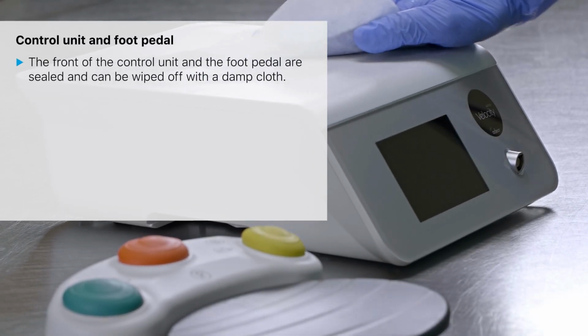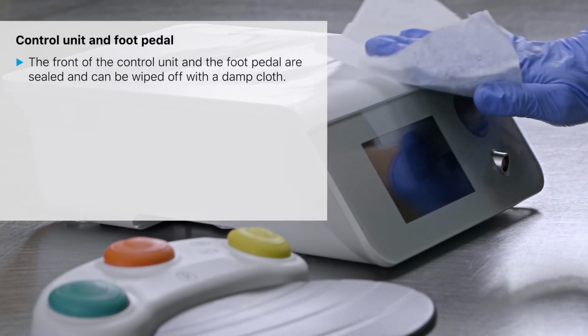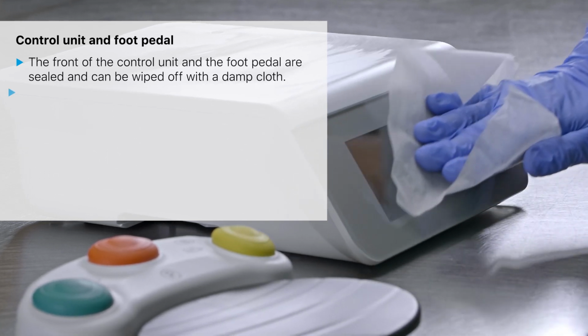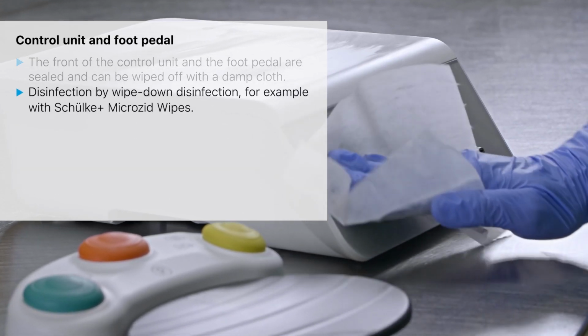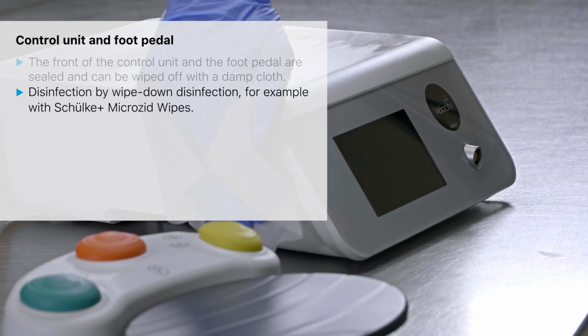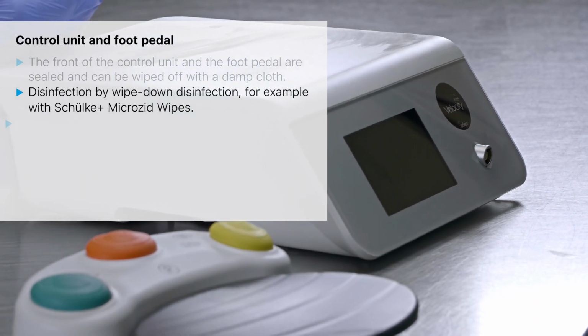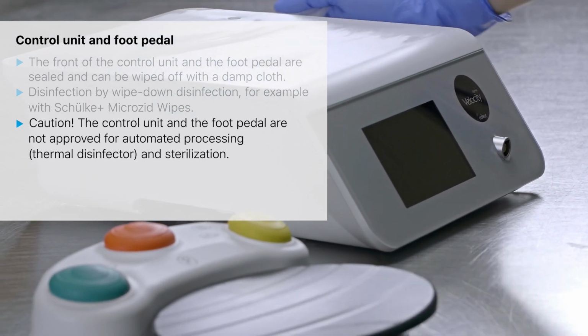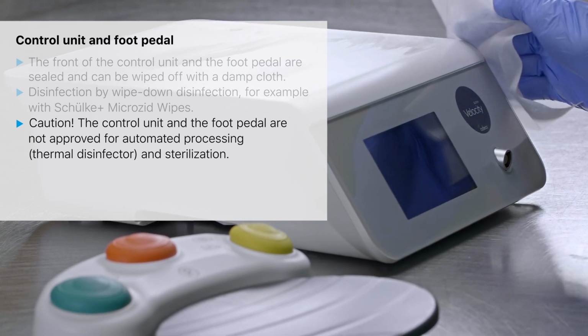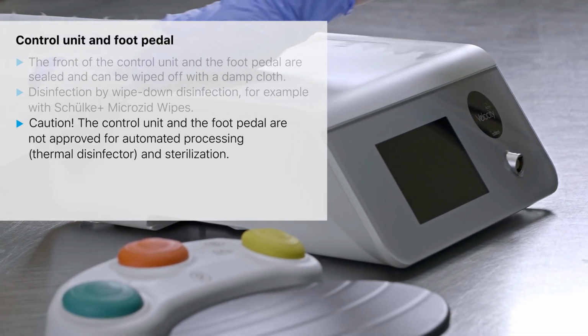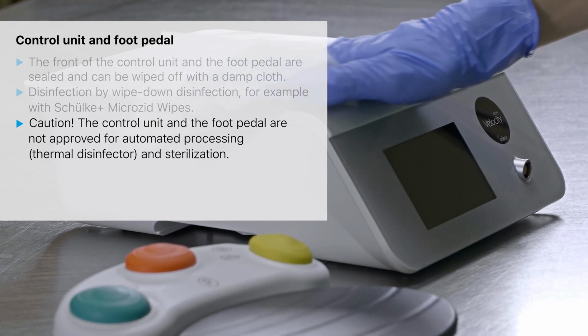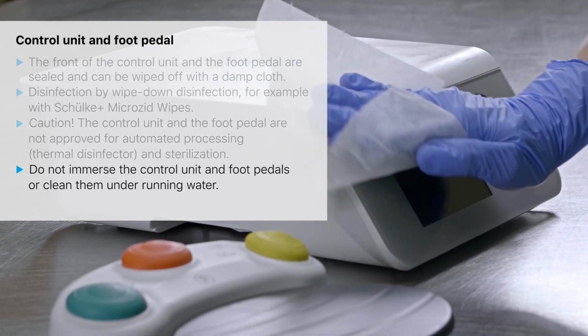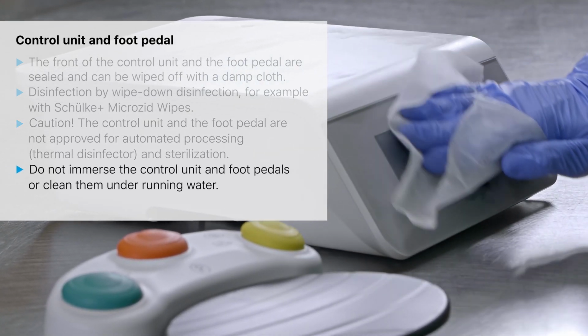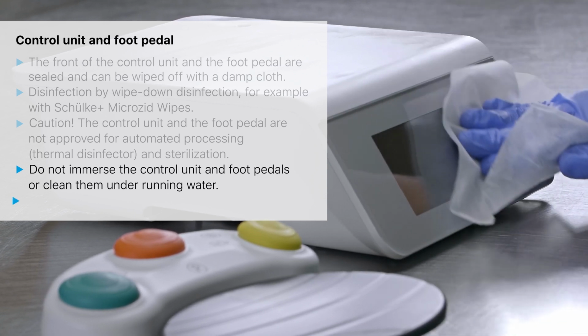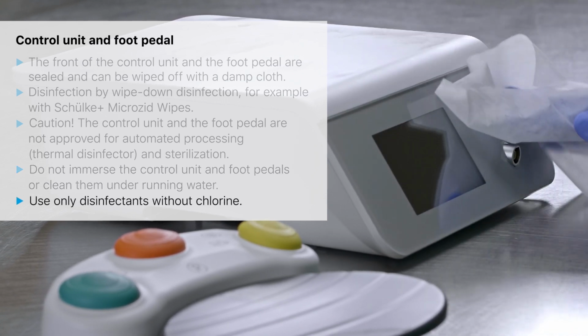The front of the control unit and the foot pedal are sealed and can be wiped off with a damp cloth. Disinfection by wipe-down disinfection, for example, with Schülke+ Microzid Wipes. Caution: the control unit and the foot pedal are not approved for automated processing, thermal disinfector, and sterilization. Do not immerse the control unit and foot pedals or clean them under running water. Use only disinfectants without chlorine.